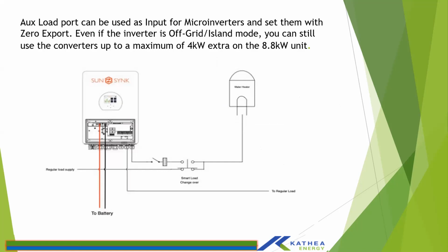This aux load port can also be used to connect micro inverters. Your client might request a system but already has micro inverters installed. So this port can actually be used as a micro inverter input port, but the rating of your micro inverters should be at most 50% of the size of the inverter. So if you are using an 8.8 kilowatt, you can have a maximum of around 4 to 4.4, basically 4 kilowatt of micro inverters connected on this load port, and the port will be used as an input to the system as well.